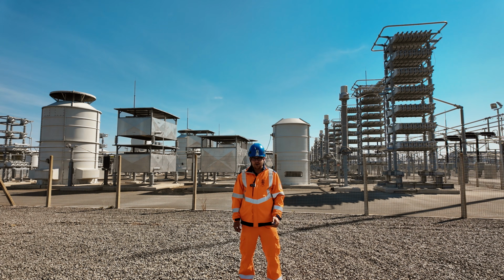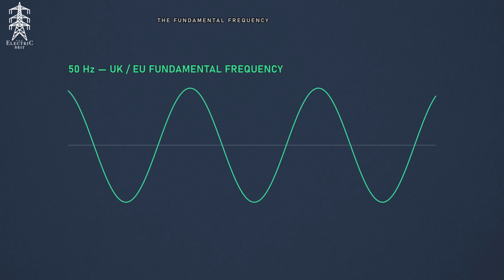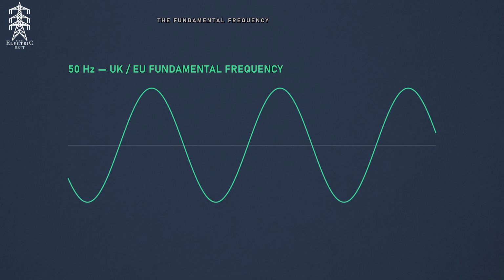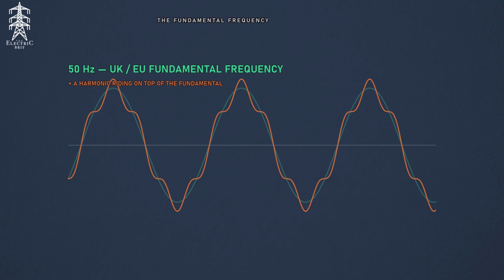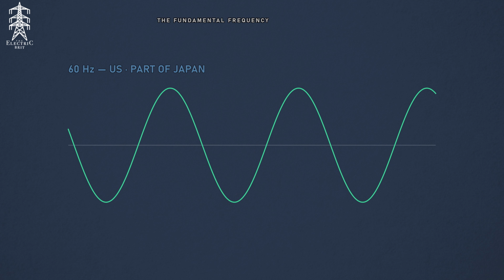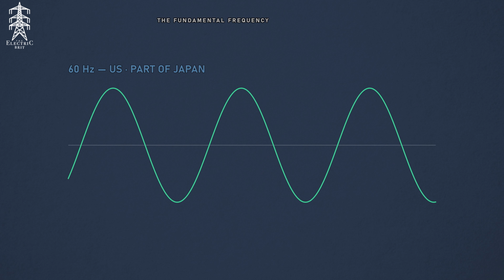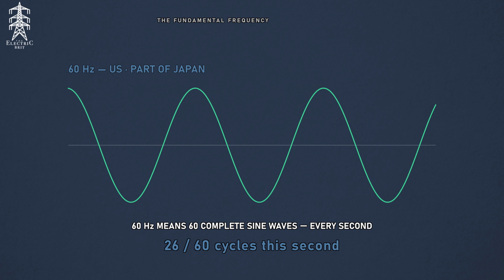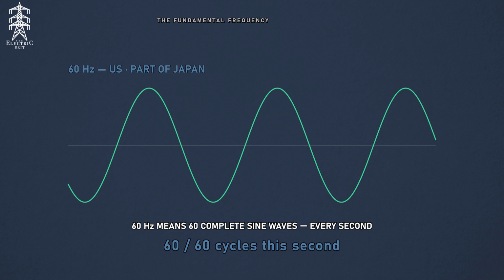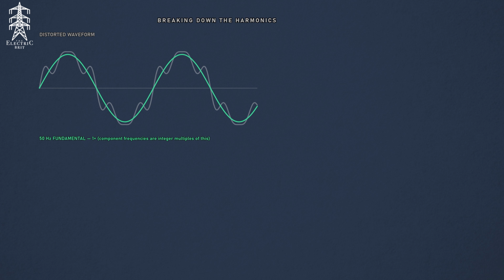The heat is wasted power, and it's generated by the harmonics because, like harmonics in sound, it's waves not like the 50 Hz we want and need here in the UK, which we call our fundamental frequency. If you're in the USA, parts of Japan or other places, that might be 60 Hz, which means 60 of those complete sine waves in a second. When that distorted waveform is broken down into its component frequencies, some of those are integer multiples of the fundamental frequency. Those are harmonics. For example, the fifth harmonic at 50 Hz is 5 multiplied by 50, so 250 Hz.